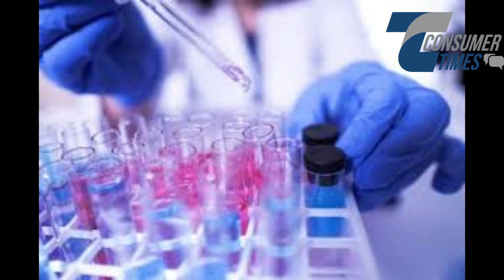The chemicals and reagents used in diagnostic tests vary in quality. High-quality reagents yield more consistent and accurate results. Labs that use cheaper, low-grade reagents to cut costs may produce variable or less reliable results. NABL accreditation helps ensure that accredited labs use standardized reagents, but not all labs are equally strict about quality. Even when the same testing methodologies and equipment are used, interpreting results might vary slightly from lab to lab. Some labs might use different reference ranges, making the same result appear within or outside the normal range, causing variations in reported values. Reference ranges depend on calibration with the local population or on the equipment used, so a minor difference in interpretation can impact reported outcomes.